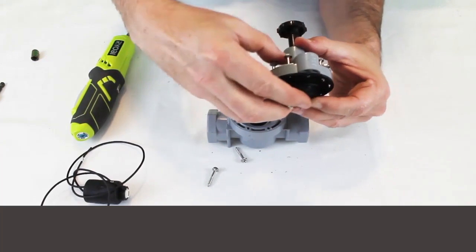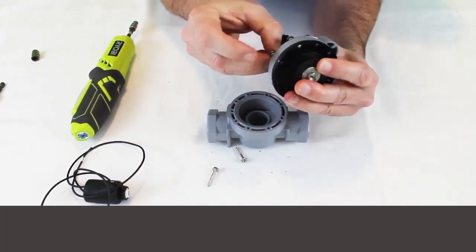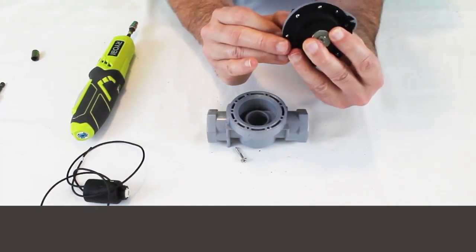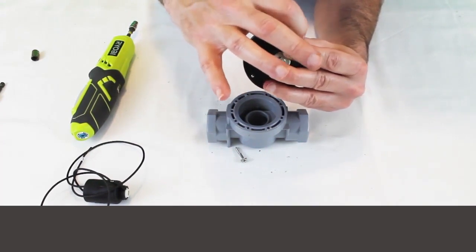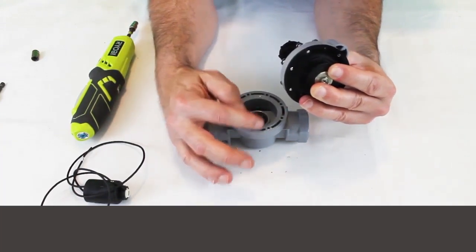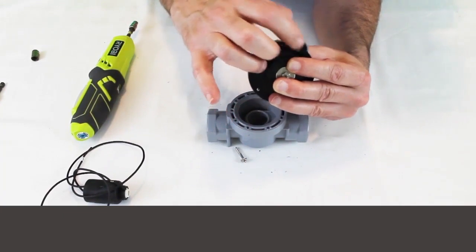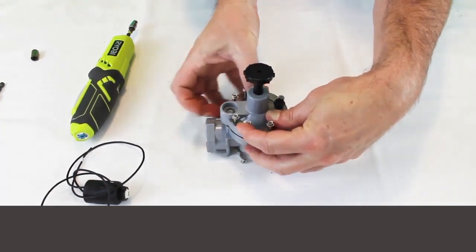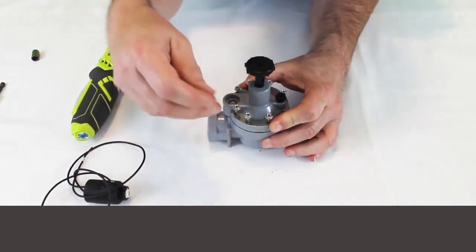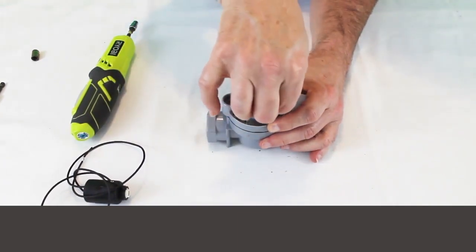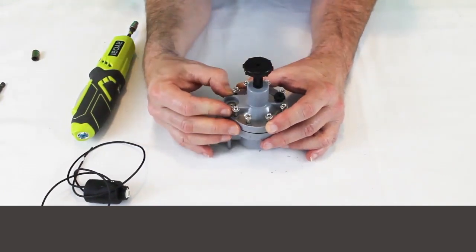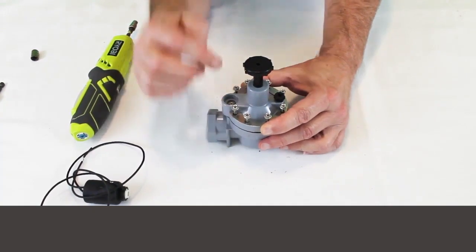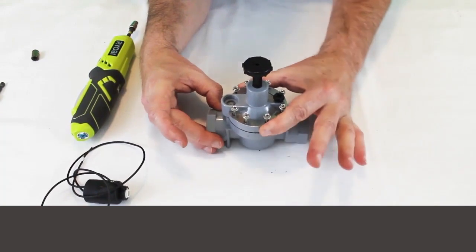Spin this around and get our last two screws on. If you've ever tried to rebuild one of these, you'll know what I'm talking about—this one's a little difficult to get right. Sometimes if you put it back together wrong and this diaphragm gets out of place or spins around or even folds over, then you're going to screw up the diaphragm and it's going to cause a leak in it. We're going to spin it back around here, line it up and set it down on there. The screws being in here are going to line it up. We've got one more that we didn't put in, but that's okay. As long as you've got the majority of them in there, it's going to hold it in place and put it right back where it's supposed to be. Because the little raised nub on here fits down into the hole for the solenoid pilot tube, it's going to line up really good and set into place.